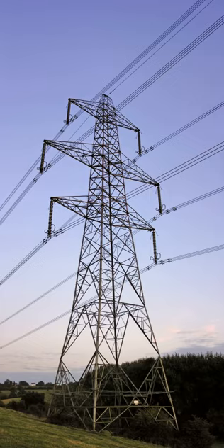High-voltage direct current (HVDC) transmission lines are either monopolar or bipolar systems. With bipolar systems, a conductor arrangement with one conductor on each side of the tower is used. On some schemes, the ground conductor is used as electrode line or ground return. In this case, it had to be installed with insulators equipped with surge arrestors on the pylons in order to prevent electrochemical corrosion of the pylons.